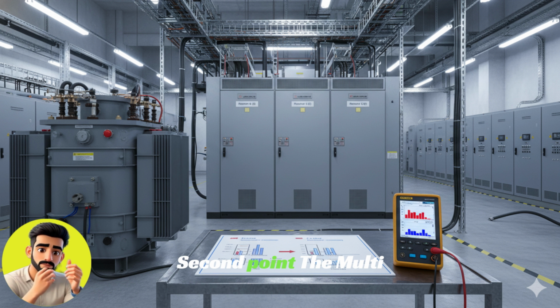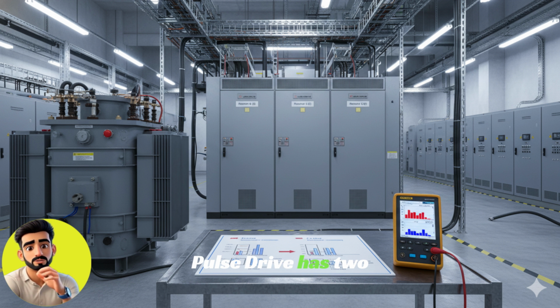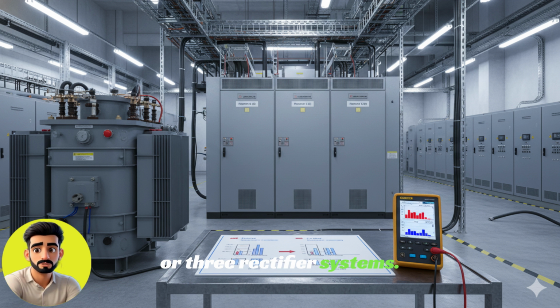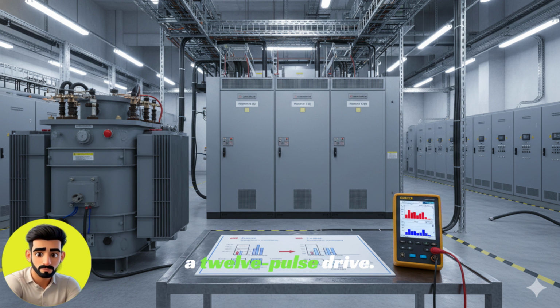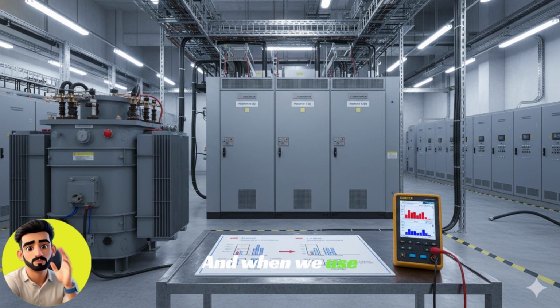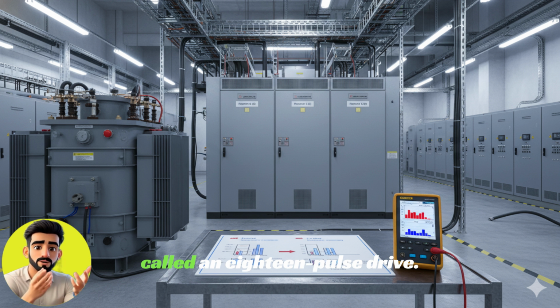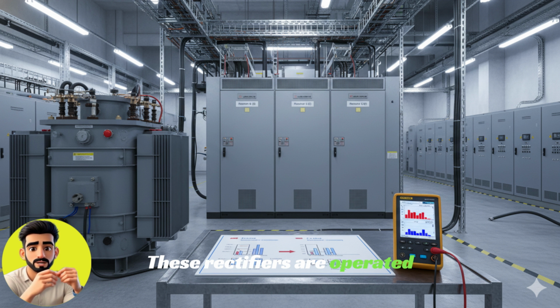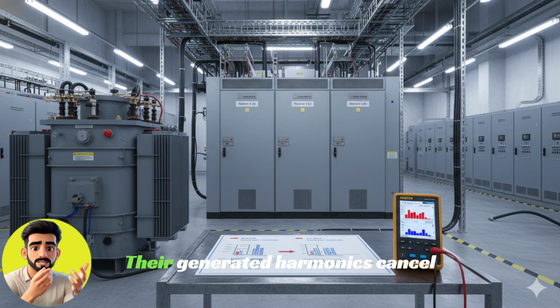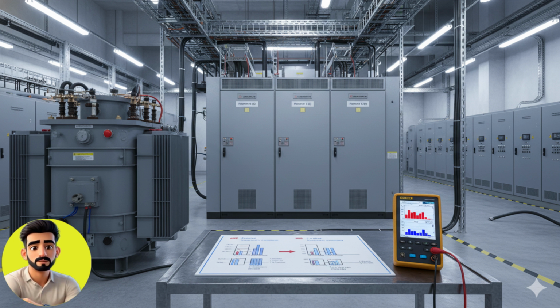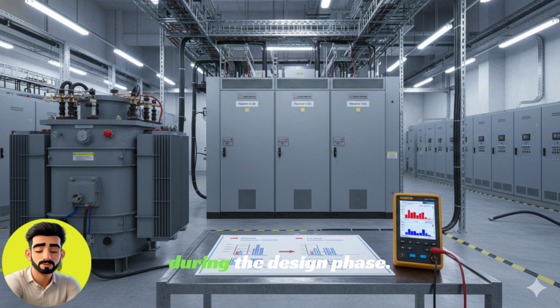Second point. The multi-pulse drive has 2 or 3 rectifier systems. When we use 2 rectifiers, it is called a 12-pulse drive. And when we use 3 rectifiers, it is called an 18-pulse drive. These rectifiers are operated at different angles. Their generated harmonics cancel each other out. This cancellation is achieved during the design phase.